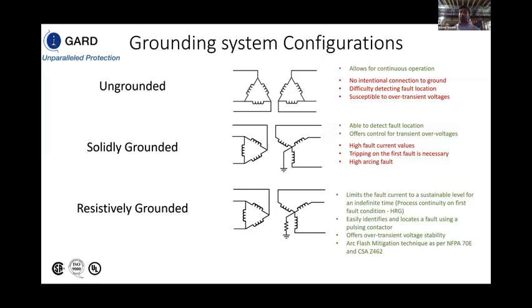In addition to that, it's very difficult to locate faults in this type of system since there's no ground return path for the fault to circulate through. So what the North American market did was they addressed this with the solidly grounded system, where you have a delta to Y configured transformer, and typically the X0 point of that transformer is solidly grounded to ground.